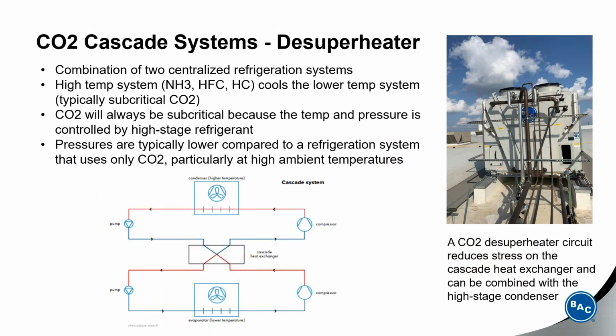Switching gears a little bit, I wanted to highlight some areas where we've seen our customers use the Trillium adiabatic product in their refrigeration systems, specifically CO2 systems. A CO2 cascade system is a combination of 2 centralized refrigeration systems. A low stage or low temperature system, typically consisting of CO2, is cooled by a higher stage, higher temperature system, typically with an HFC refrigerant.